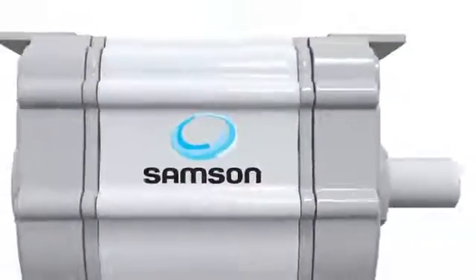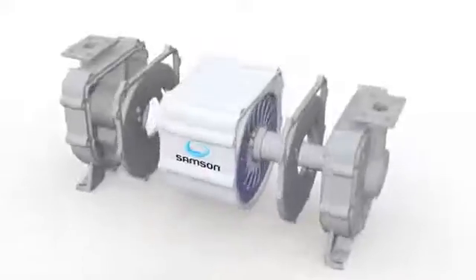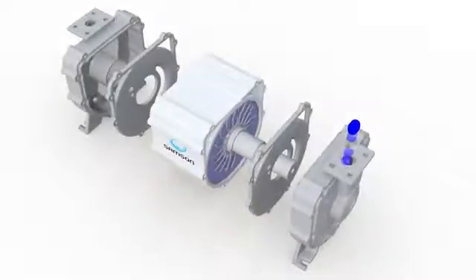A liquid ring pump is a rotating positive displacement pump that operates with no contact between the moving parts. The liquid ring pump compresses gas by rotating a vaned impeller located eccentrically within a cylindrical casing.